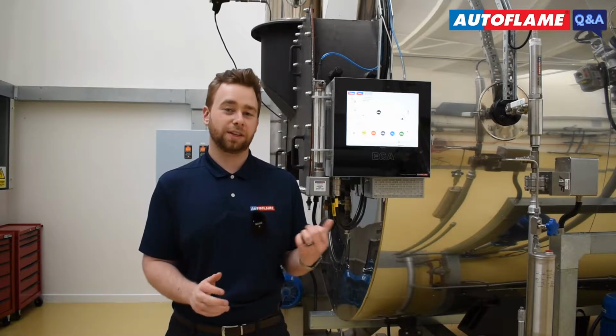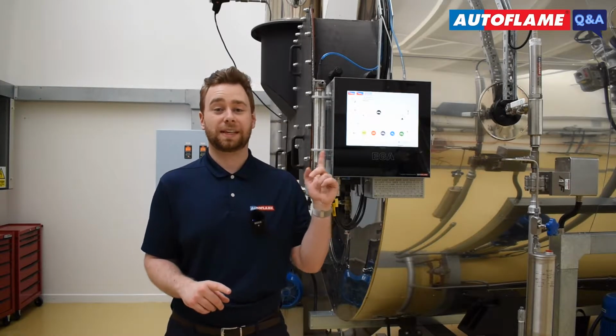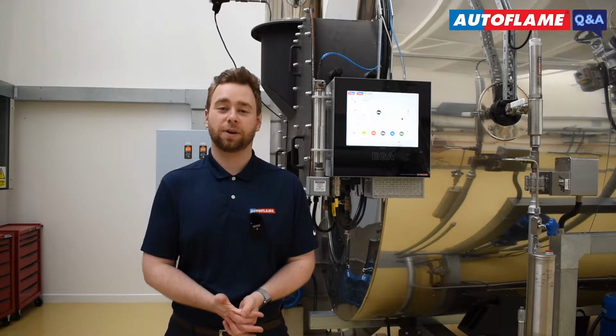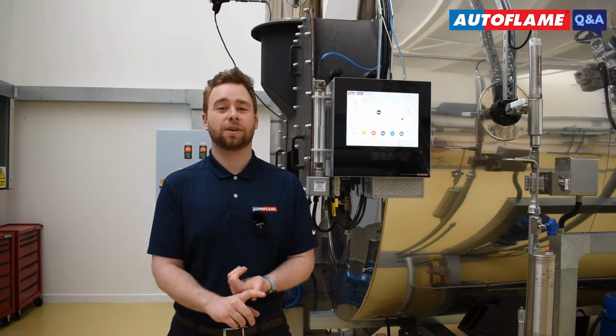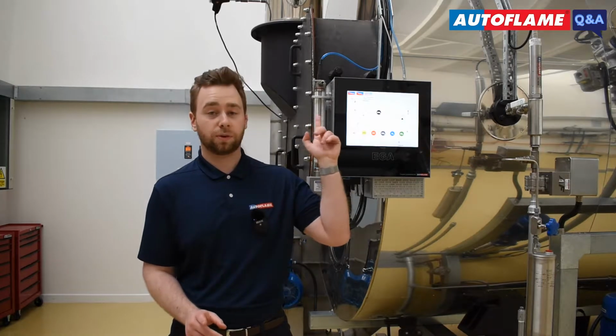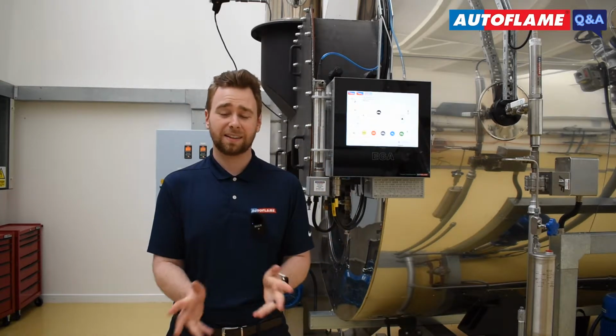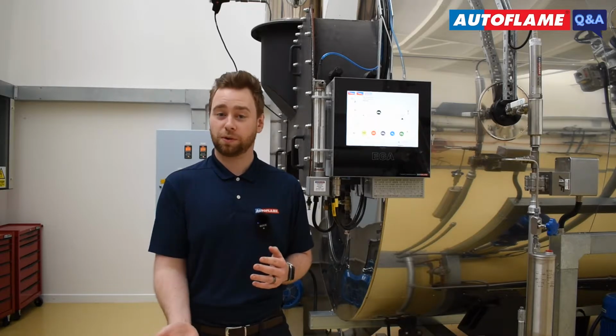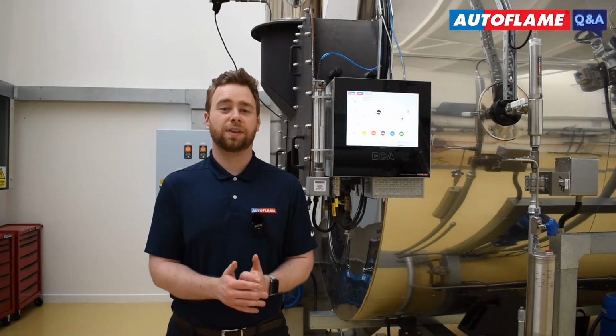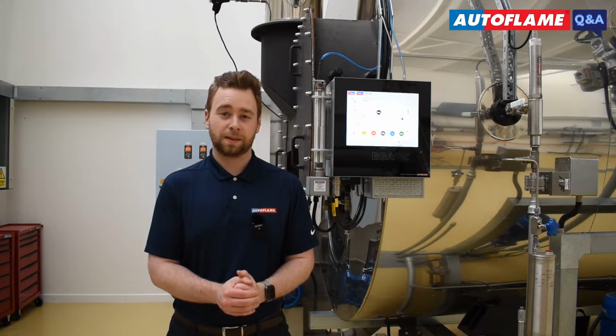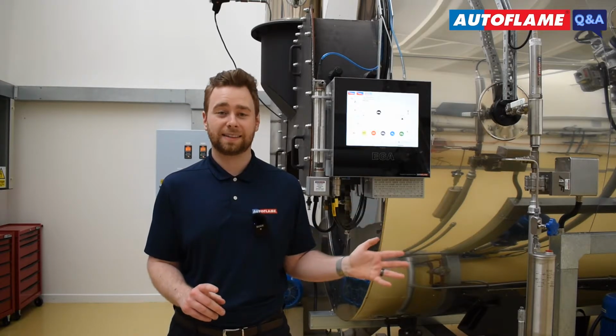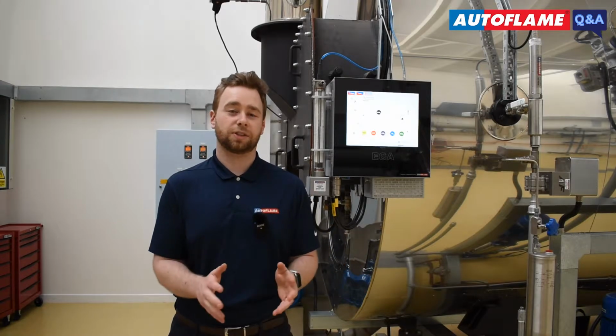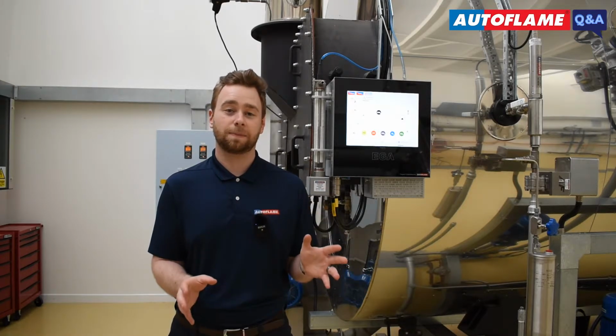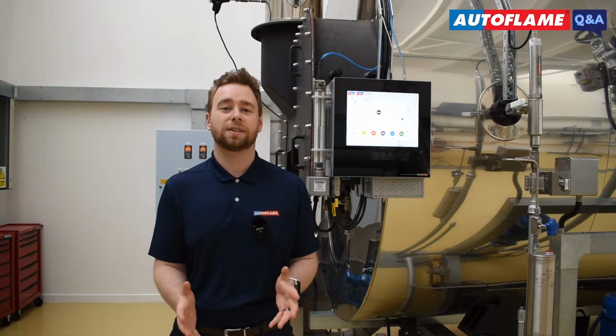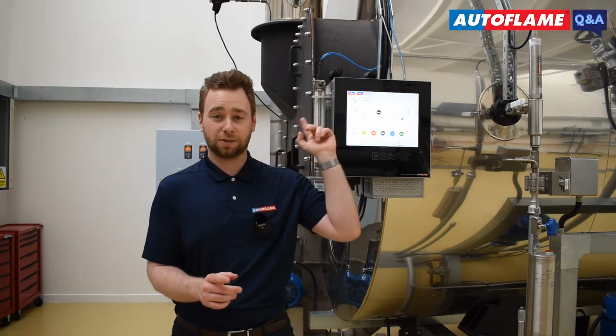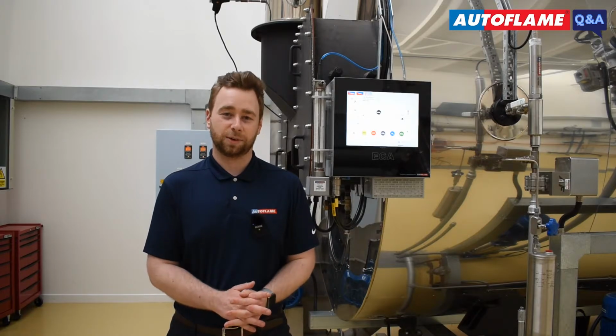Because of the nature of the environment the EGA operates in and the composition of exhaust gases analysed, your EGA will require periodic servicing. This is to ensure accurate and reliable measurement of your boiler's stack emissions. This emissions data is used to report your emissions, but also feeds in directly with the MM's combustion trim function. This trim function will modulate your burner's air damper or the burner's combustion air fan VFD when your stack emissions deviate from commissioned levels. Therefore, it's imperative that the readings that the EGA measures in the stack are reliable and accurate.